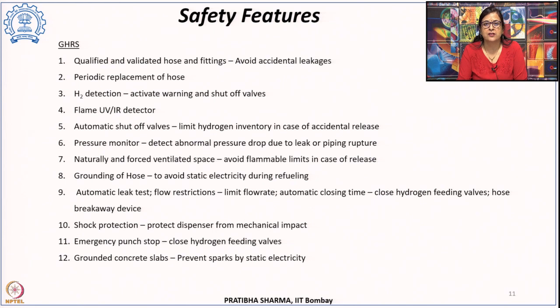When it comes to gaseous hydrogen refueling stations, there is a series of safety measures which are taken so as to avoid any sort of accidents. Like the hose and fittings, which are qualified and validated as per the standards so as to avoid any accidental leakage. At the same time, these hose and fittings are periodically tested, checked, monitored and replaced whenever required. There are hydrogen detectors at refueling stations which activate warnings and then shut off the valves. There are flame detectors present at the hydrogen refueling station. There are automatic shut off valves which limit the hydrogen inventory in case of accidental release.